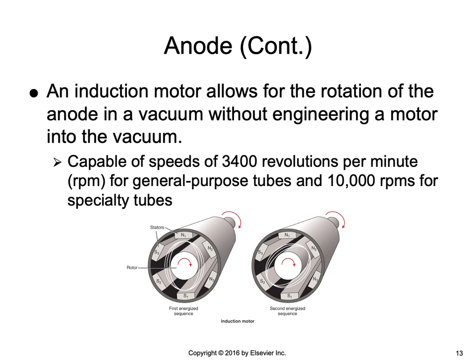Using an induction motor allows for the rotation of the anode in a vacuum tube without engineering a motor into the vacuum. Such motors are capable of rotating the anode at speeds of 3,400 revolutions per minute for general purpose tubes and 10,000 RPMs for specialty tubes. This figure shows an induction motor — the operation of the opposing pairs of stators in sequence ultimately causes rotation of the rotor.